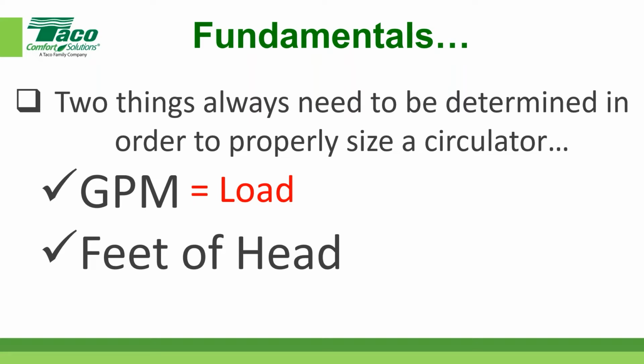The other thing I'll point out is panel rads are primarily used in Europe, and we see that as a standard everyday hydronic heating system over there. All day long they're designing those at a 20-degree delta T, but their 20-degree delta T is Celsius. So to us folks in North America, that's 36 degrees Fahrenheit. So don't worry about doing panel rads at 30 degrees. The folks across the pond are doing it at 36 all day long and have been quite successful with it. So anyway, hope that helps.